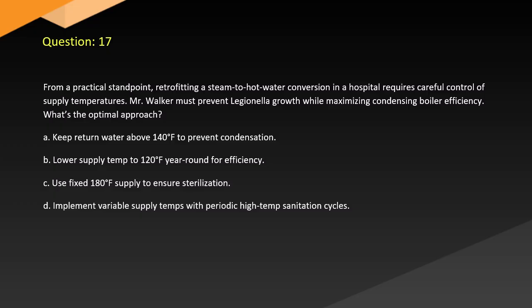A. Keep return water above 140 degrees Fahrenheit to prevent condensation. B. Lower supply temp to 120 year-round for efficiency. C. Use fixed 180 degrees supply to ensure sterilization. D. Implement variable supply temps with periodic high-temp sanitation cycles.